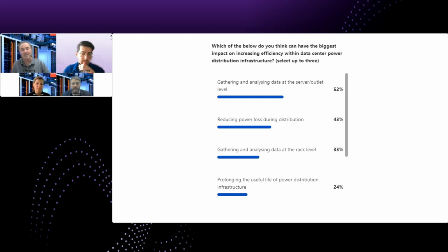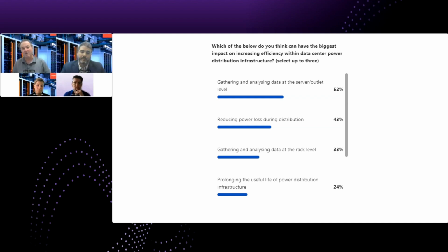There are some gains there, and depending on scale, they can be significant—both in how efficiently your server runs, and secondarily in your distribution system, by not taking 480 volts all the way down to 120, which is essentially what 208 is—two 120 volt legs out of phase that get you your 208. This was talked about a lot years ago, but it's still relevant today: there are efficiency gains in distributing power at higher voltages within your data center.